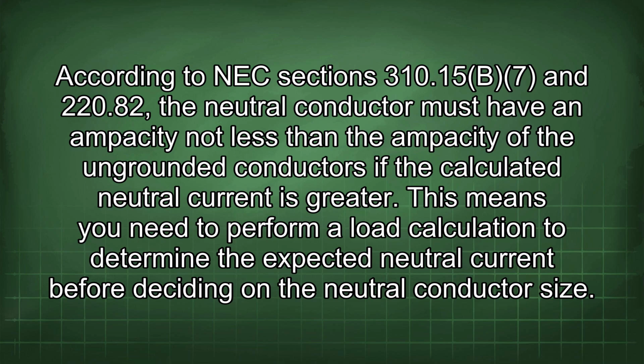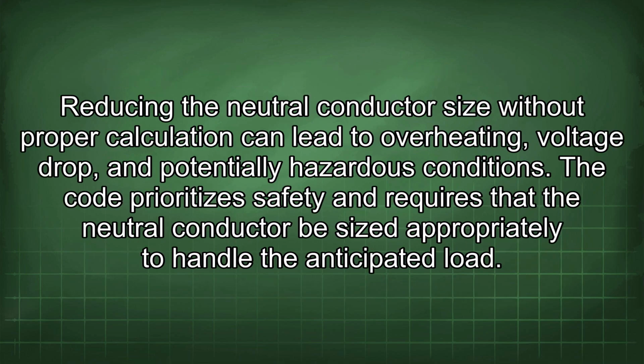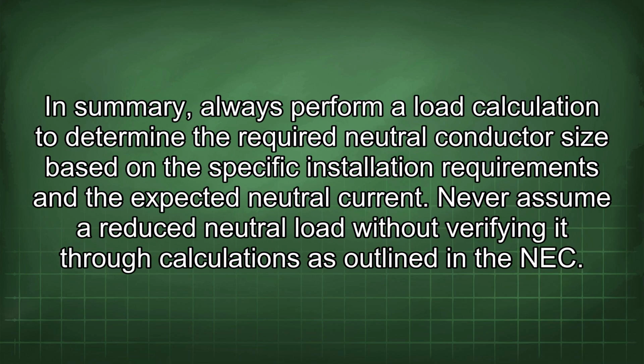This means you need to perform a load calculation to determine the expected neutral current before deciding on the neutral conductor size. Reducing the neutral conductor size without proper calculation can lead to overheating, voltage drop, and potentially hazardous conditions. The code prioritizes safety and requires that the neutral conductor be sized appropriately to handle the anticipated load. In summary, always perform a load calculation to determine the required neutral conductor size based on the specific installation requirements and the expected neutral current. Never assume a reduced neutral load without verifying it through calculations as outlined in the NEC.